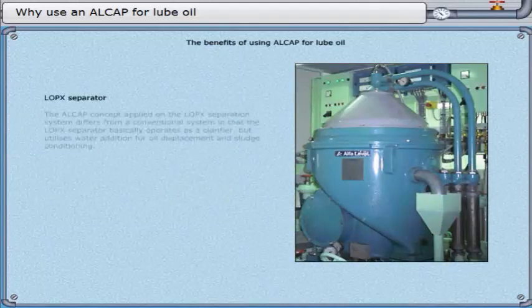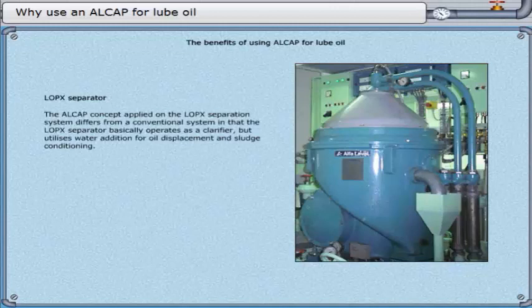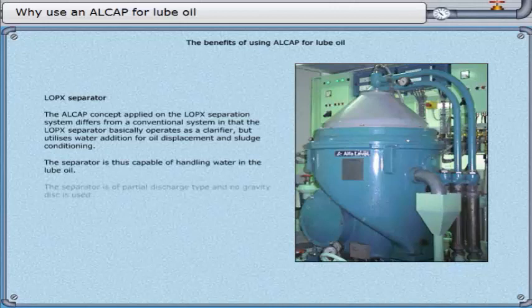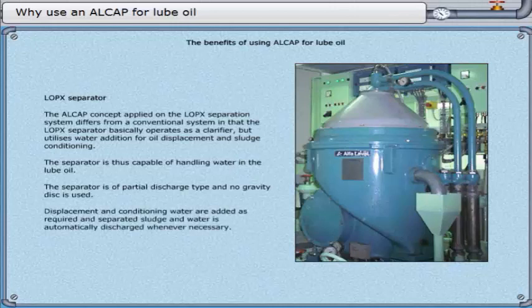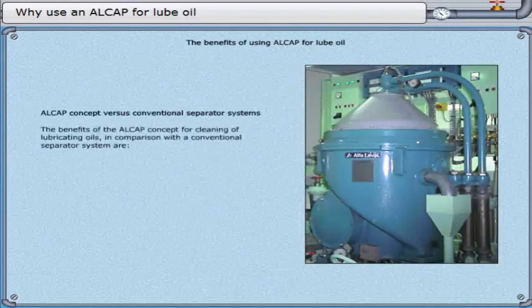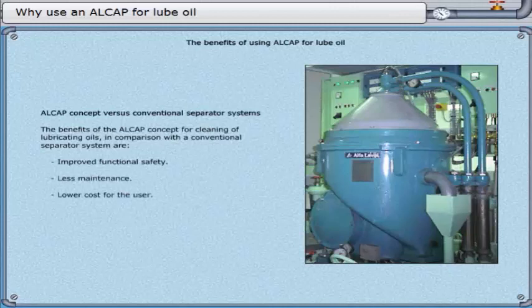The Alcap concept applied on the LOPX separation system differs from a conventional system in that the LOPX separator basically operates as a clarifier, but utilizes water addition for oil displacement and sludge conditioning. The separator is thus capable of handling water in the lube oil. It is of partial discharge type, and no gravity disk is used. Displacement and conditioning water are added as required, and separated sludge and water are automatically discharged whenever necessary. The benefits of the Alcap concept for cleaning of lubricating oils, in comparison with a conventional separator system, are improved functional safety, less maintenance, lower cost for the user, and being more suitable to modern-day lubricating oil demands.